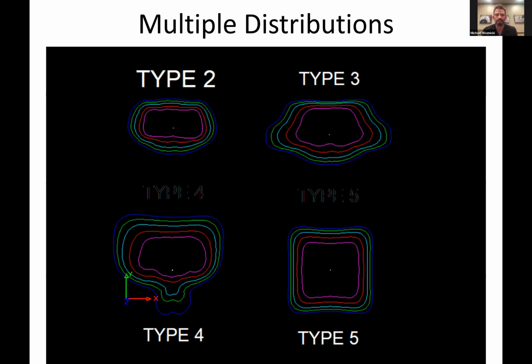So when we're looking at streetscape designs, if we need to do a large coverage of a swath or an area, the Type 5 does an excellent job of actually focusing the lumens into the corners and really matching up rather than just having it essentially dumped down. And when we get into sides where we want to mitigate some backlight, whether it's residential areas or some businesses, and keep everything pushed forward onto the street, we would look at a Type 3 or a Type 4. And there'll be some small pathways where we're looking at a Type 2.